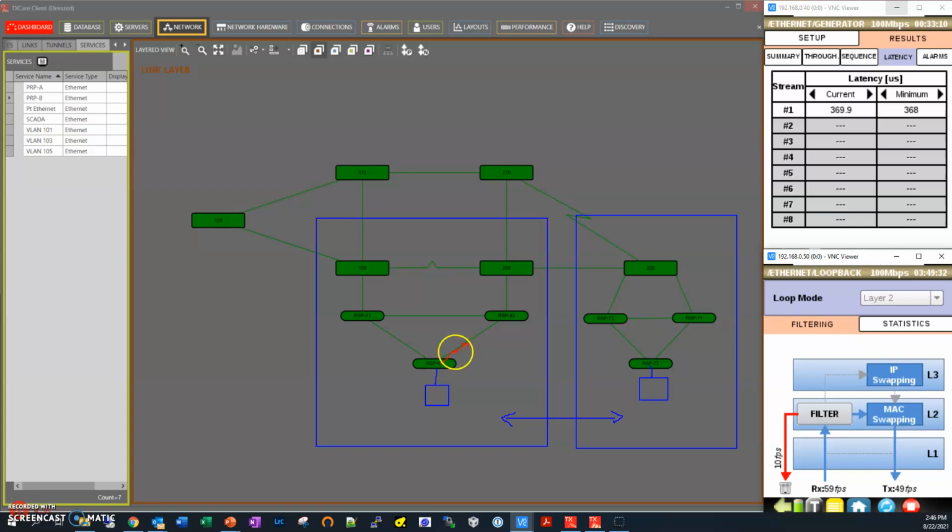So let's say a red one, and let's say its duplicate copy is green, so two copies are going to go out this way for the same GOOSE message. And what happens is that it'll reach this RSP63, and this one is a gateway. So in other words, it's not only going to continue sending it in the ring, but it's also a PRP gateway, so it'll send a copy up into, let's say, this PRP.